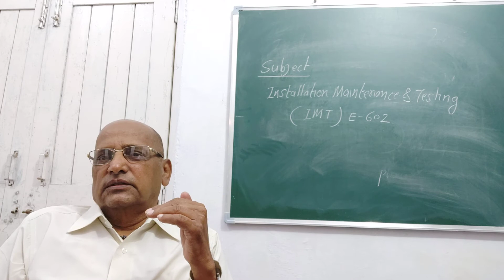Because it should have the operating height for the operators who control this panel for controlling the LT lines for the supply. So this height must be taken according to the drawing, and it is approximately, I am telling, 1.5 meters from the ground, so that a normal height person can approach and work on this panel.